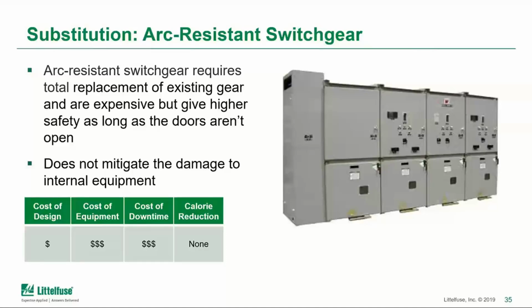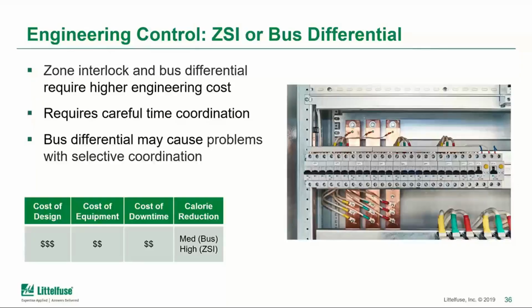An engineering control that can be added is zone selective interlocking and bus differential protection. These schemes both do a really good job of mitigating the arc flash risk, but the return on investment will probably depend on how complex the system is overall. Both of these options require engineering resources on the front end, ensuring that the breaker settings are configured. In a retrofit application, implementing these schemes may require the addition of CTs, potentially new breakers.